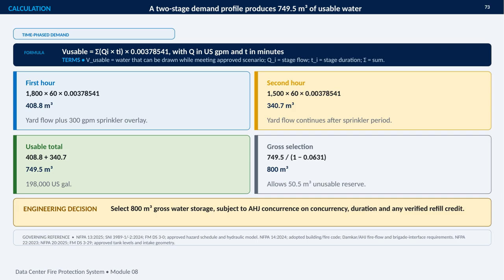During the second hour, demand drops to 1,500 gallons per minute for another 60 minutes, producing 340.7 cubic meters as yard flow continues after the sprinkler period. Adding those two stages gives 749.5 cubic meters, or approximately 198,000 US gallons, that can actually be drawn while meeting the approved scenario. The gross tank selection is higher because 6.31% is treated as unusable reserve. Dividing by the usable fraction gives a required gross capacity of about 800 cubic meters, leaving 50.5 cubic meters unavailable for drawdown. The engineering decision is therefore to select an 800 cubic meter gross tank, subject to AHJ concurrence on concurrency, duration, and any verified refill credit.